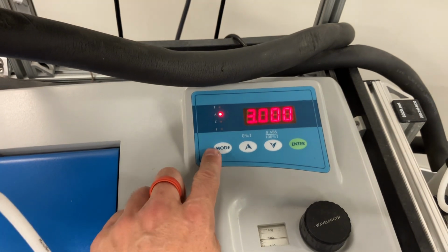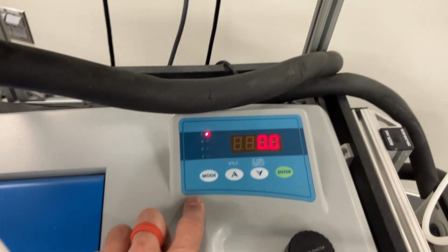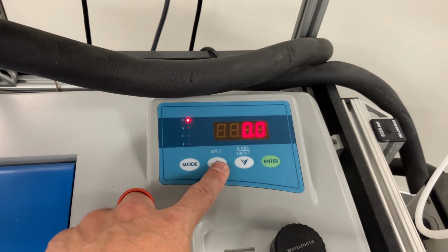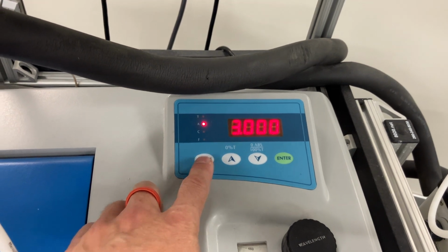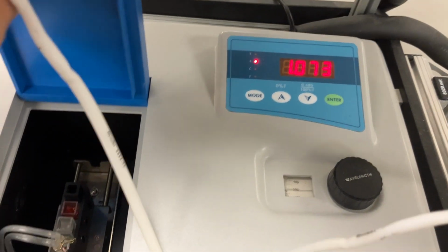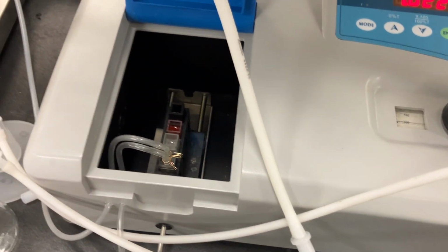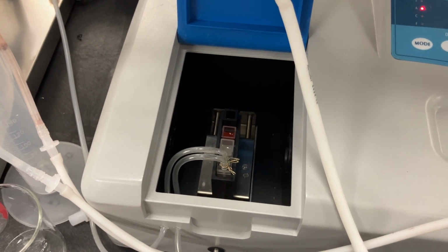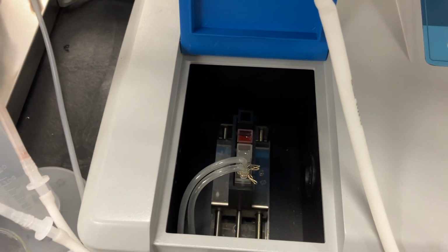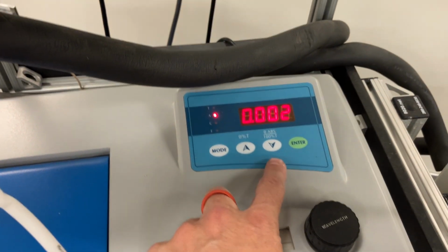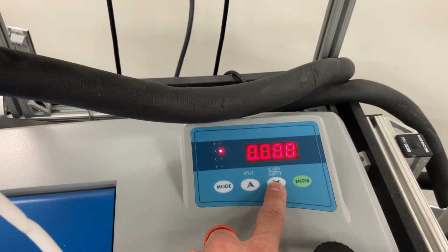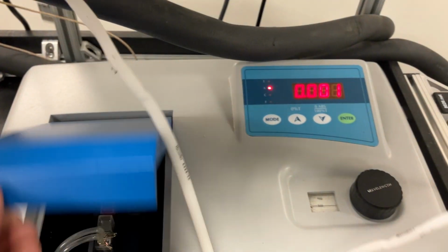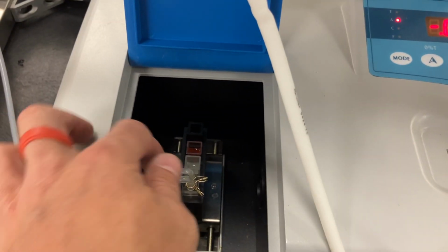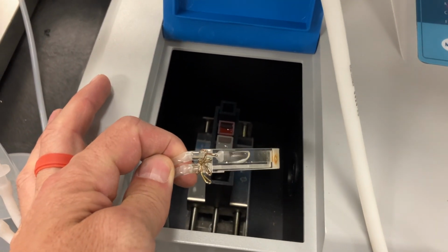Then I can go to transmittance. It should read 0. If it doesn't, you can hold this down. Then you can go to absorbance, and you can go to your 0 absorbance index, which in this case is distilled water, and it should read 0 as far as absorbance goes, which it does. And then you can use the flow cuvette.